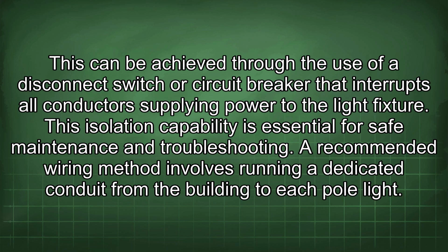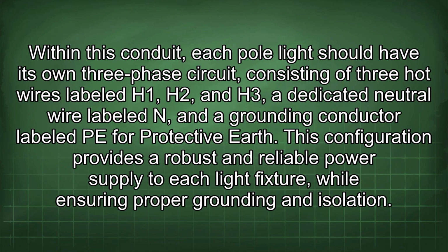A recommended wiring method involves running a dedicated conduit from the building to each pole light. Within this conduit, each pole light should have its own 3-phase circuit consisting of 3 hot wires labeled H1, H2, and H3, a dedicated neutral wire labeled N, and a grounding conductor labeled PE for protective earth. This configuration provides a robust and reliable power supply to each light fixture, while ensuring proper grounding and isolation.